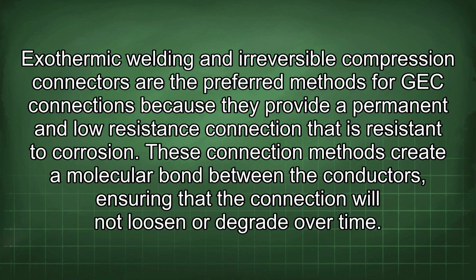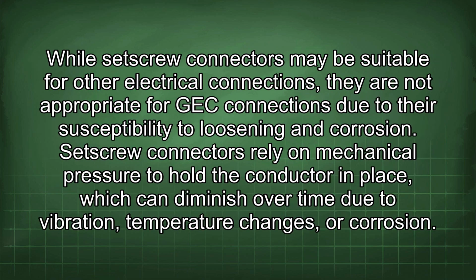These connection methods create a molecular bond between the conductors, ensuring that the connection will not loosen or degrade over time. While set screw connectors may be suitable for other electrical connections, they are not appropriate for GEC connections due to their susceptibility to loosening and corrosion.